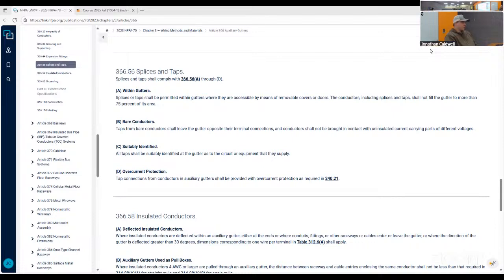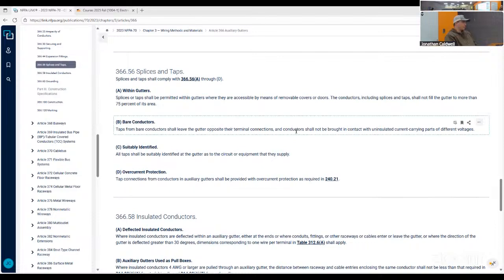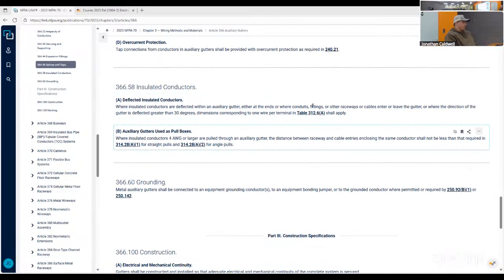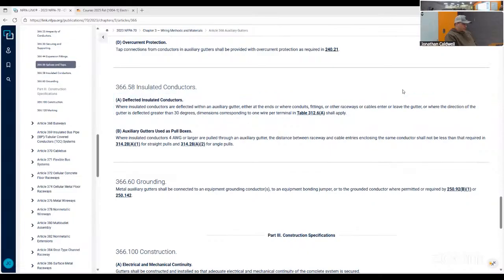And then overcurrent protection for the tap conductors. Insulated conductors are deflected within the auxiliary gutter either at the ends where the conduits, fittings, or other raceways or cables enter or leave the gutter, or where the direction of the gutter is deflected greater than 30 degrees, with dimensions corresponding to one wire per terminal. So that's just bending radius, essentially. Where insulated conductors 4 AWG or larger are pulled through an auxiliary gutter, the distance between the raceway or cable entries enclosing the same conductor shall not be less than the required 314.28(A)(1) and (A)(2).